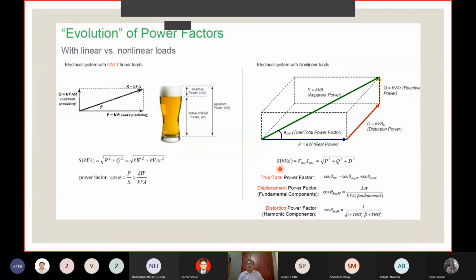So now the revised power triangle or new power triangle, S kVA will be equal to square root of P square plus Q square plus D square. So this D square is the distortion power, newly added. Now this is what is going to cause kVAH to be more than the kWH. So not only power factor, we also have to minimize the distortion factor. This is the importance for states which have gone for kVAH billing to also address the distortion factor.